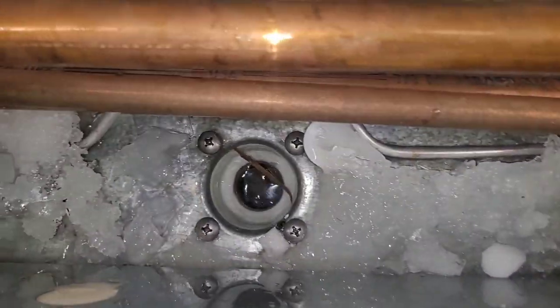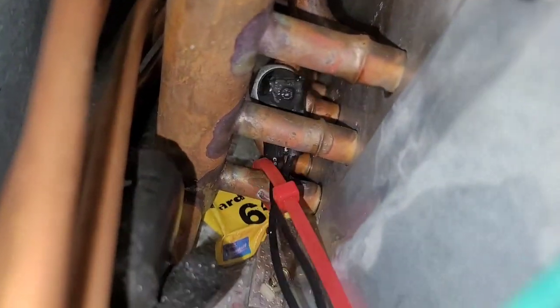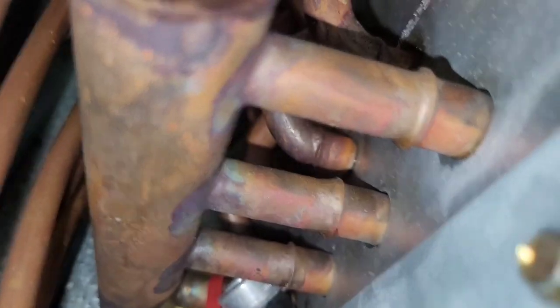This sure is a lot of ice. Let's see the drain — looks like it's draining. So far just washing it out. It's had a lot of trash in it. The drain was a little clogged but not very much. I haven't yet tested the fans, but I do see that this switch is not mounted like it's supposed to be — it's supposed to be touching the pipe and it's not. It lost the clip.